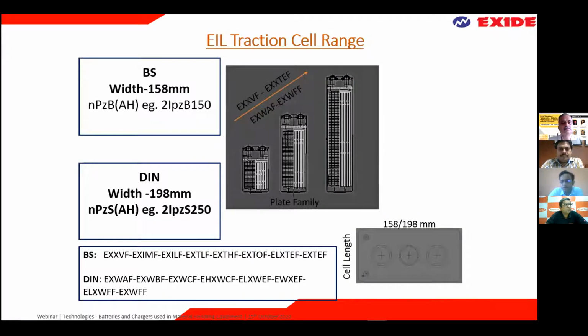Now, the system voltage depends on your particular lift truck type. For attendees in the purchase department who want to identify a particular cell type or battery type and how to choose them from catalogs, batteries generally follow a particular nomenclature. For example, if you look at the top left, there's a nomenclature like 2PZB150. The first number indicates the number of positives inside. Then for PZ, there are two types: PZP or PZS. PZB means the battery adheres to the BS standard of dimensions, and PZS means it adheres to the DIN standard of dimensions. The last numbers, like 150 or 250, represent the rated ampere hour of the battery at C5.